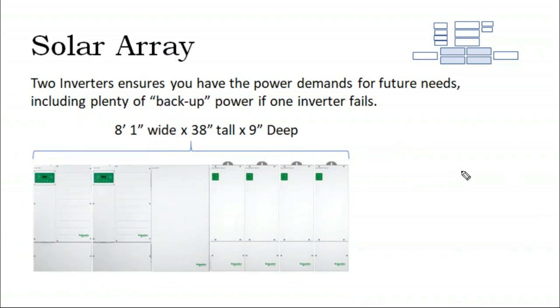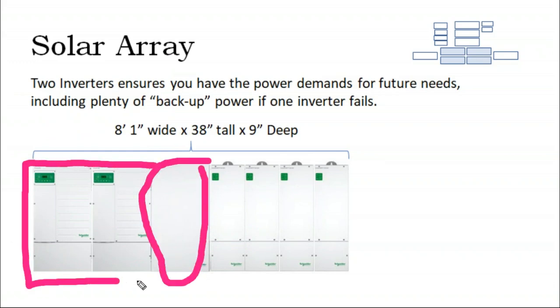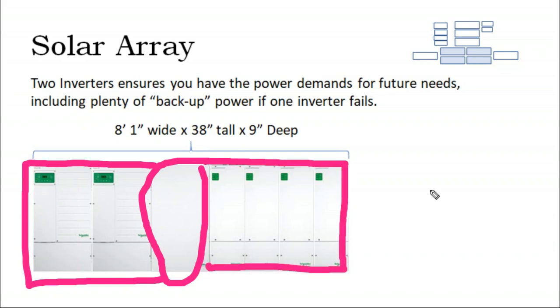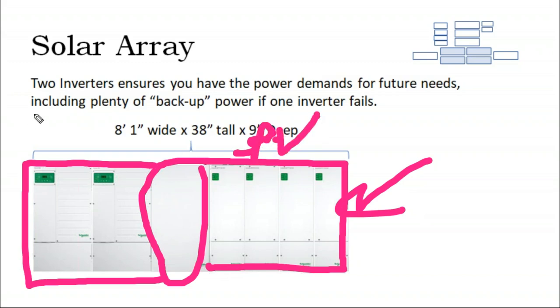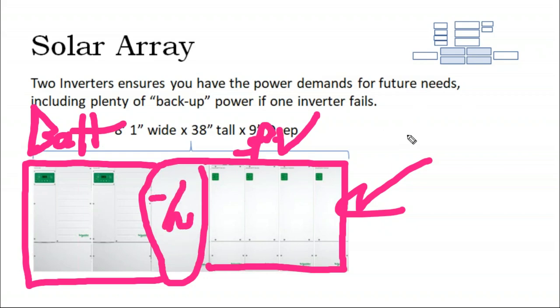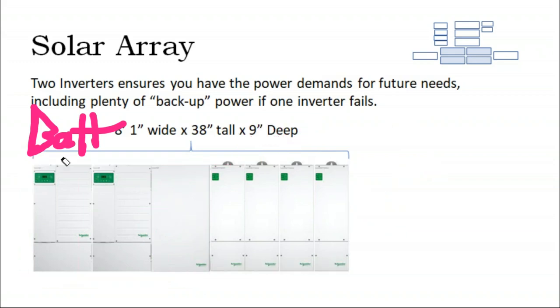And so you have your switchgear panel plus an inverter that is twice as large as the solar inverters you're used to designing with. And then on top of that, you either need the DC charge controllers or the AC coupled solar array. So you need the PV side of things, and then you have the battery side of things, and then you have the connection point, and it takes up, you're looking at three times the amount of space as a traditional solar array.